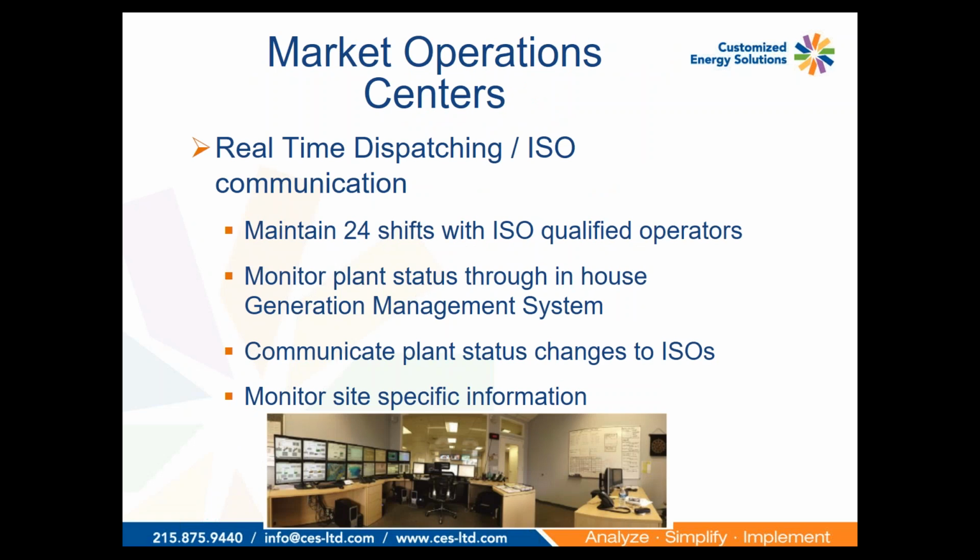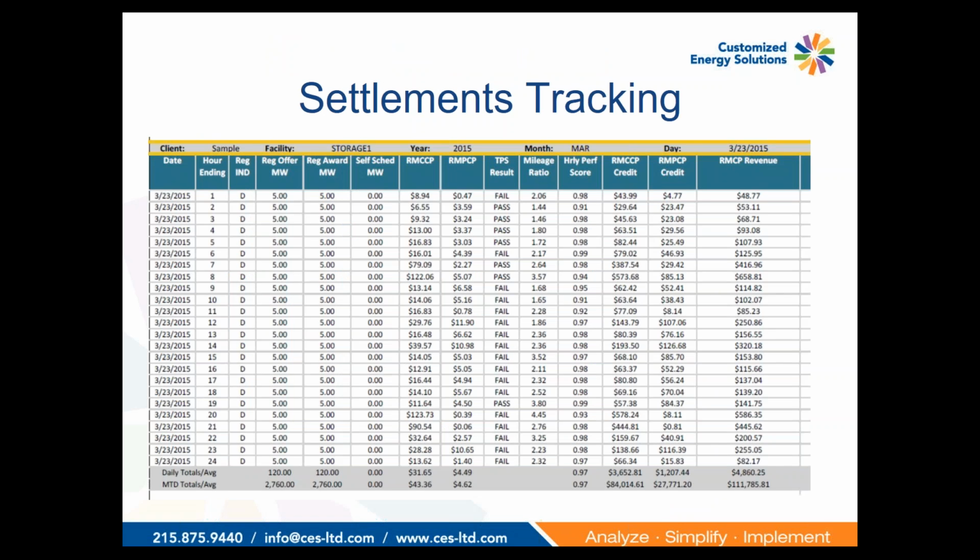So how do you make all this happen? Most of the time, we've seen storage facilities be managed or monitored by some sort of market operations center. Some of the ISOs for facilities that are providing regulation actually require there to be a 24-hour operator on standby, and again, that's because these regulation facilities contribute significantly to the reliability of the grid, and so it's very critical to the ISOs that they're able to get a hold of someone if there's any problem with those facilities.